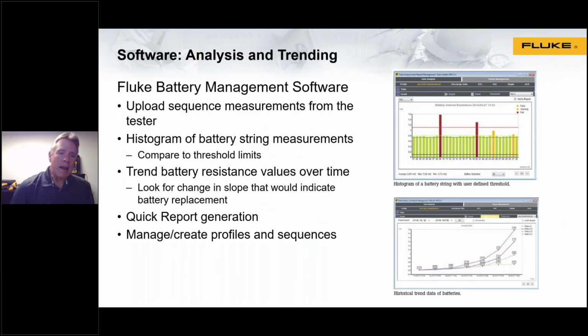The software is very useful for analysis and trending, and that's really what we're looking at. We've got a couple of different images there. One shows all the individual cells, and the tester does allow, if you know either through experience or from measuring new batteries what a good value should be, you can set that as a limit, which is indicated by the red horizontal line. Individual cell or battery measurements can be compared to that limit, and anything out of the limit, on an individual set of measurements, would be highlighted visually as a fail.